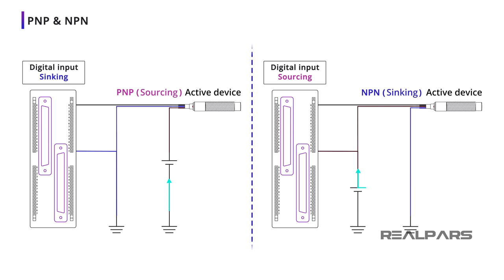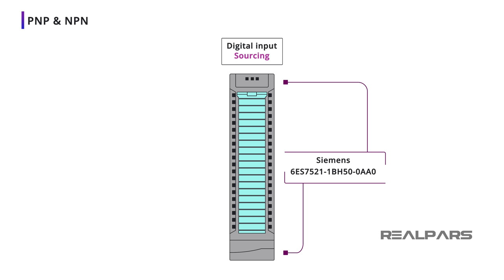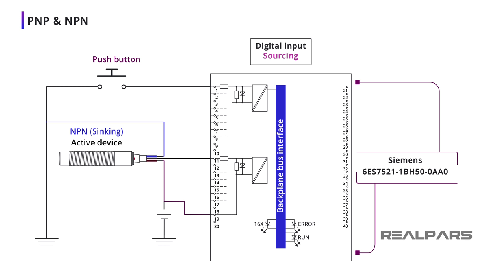Here's something to remember: an NPN device is a sinking device, and a PNP device is a sourcing device. The Siemens Digital Input Module 6ES7521-1BH50-0AA0 is a sourcing type. If you want to order this PLC module to use in your project, you can find the link in the video description. Let's connect a push-button switch and a sinking proximity sensor to two of the inputs. The current is flowing out of the PLC module because it is a sourcing type.